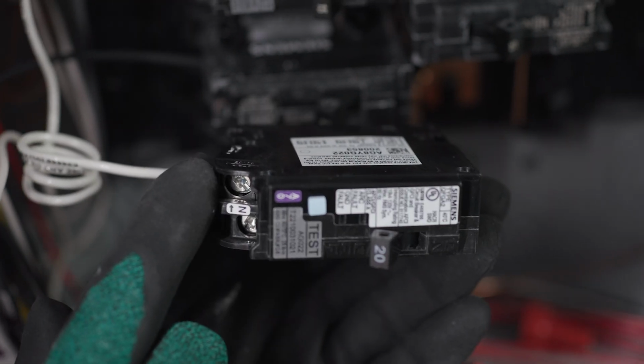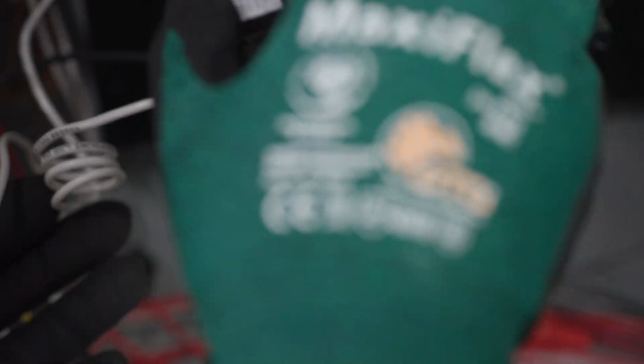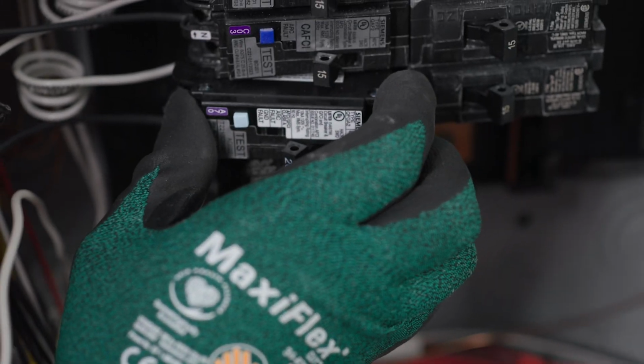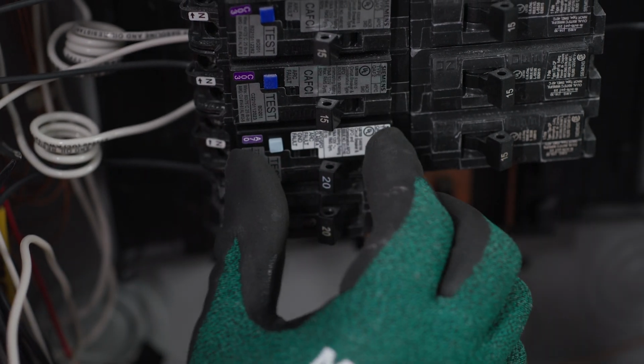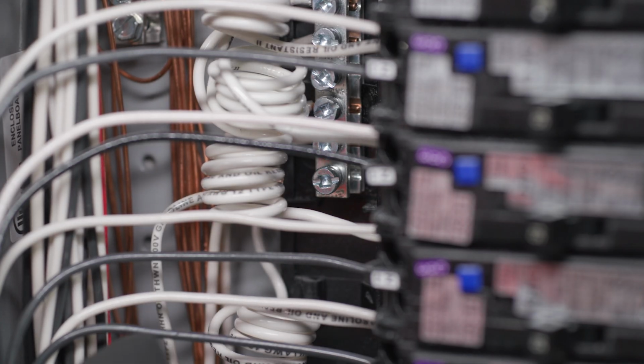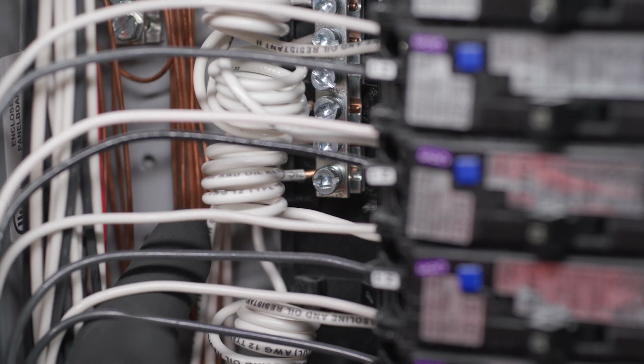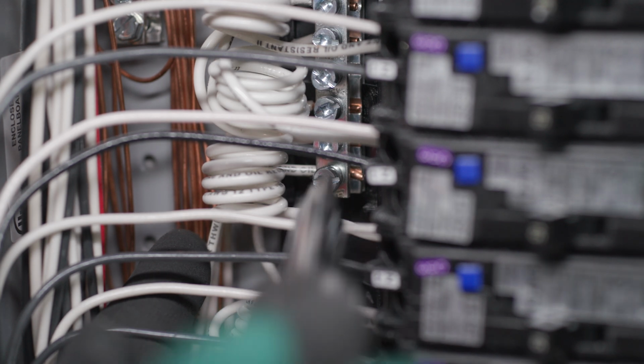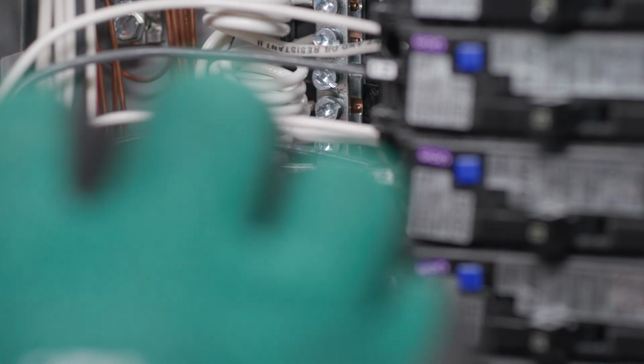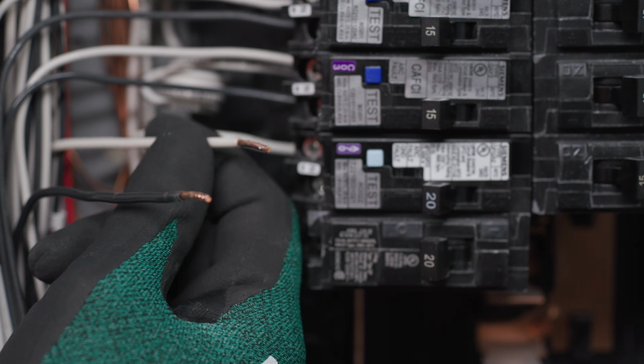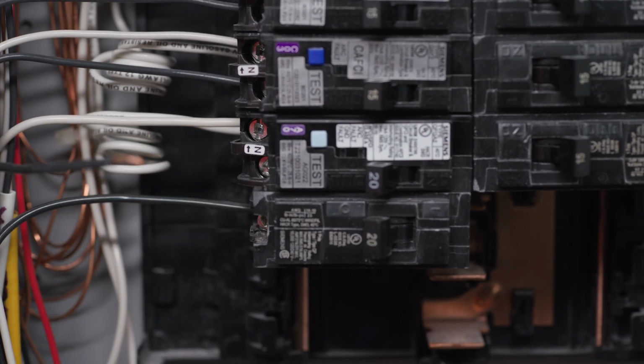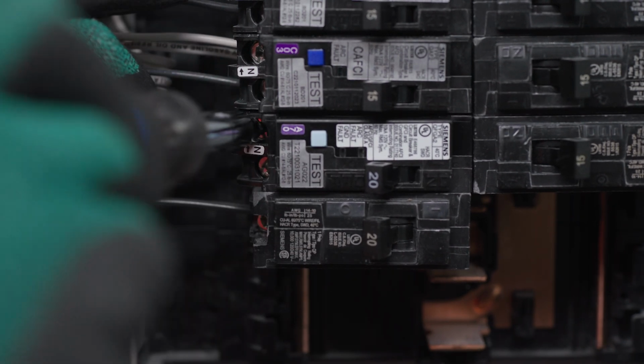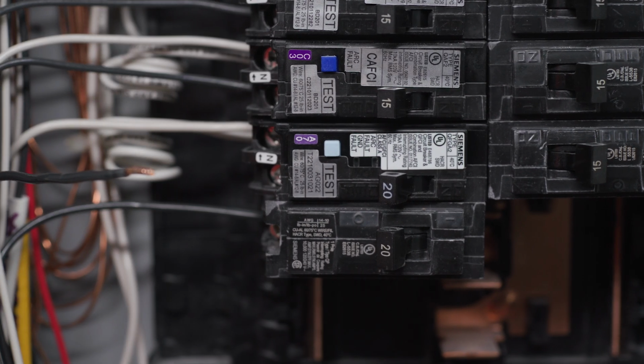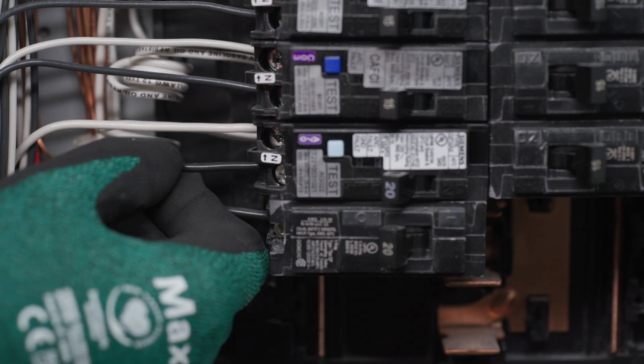Turn the AFCI breaker handle to the off position and loosen the two terminal screws. Slide the AFCI breaker into the slot and connect the coiled white wire to the neutral bus in the same position from where the white wire was just disconnected. Next, connect the white circuit wire or neutral wire to the breaker's neutral terminal. And finally, connect the black circuit wire to the breaker terminal labeled load power or black.